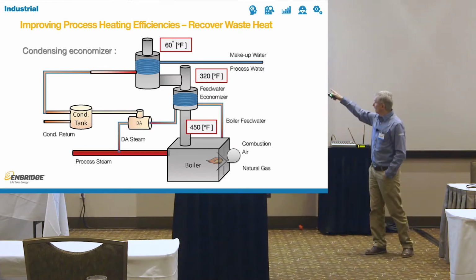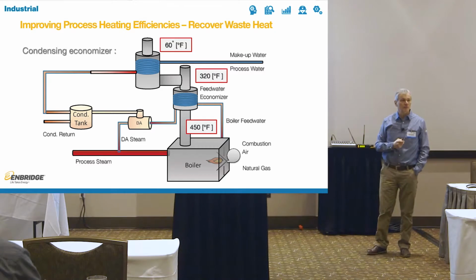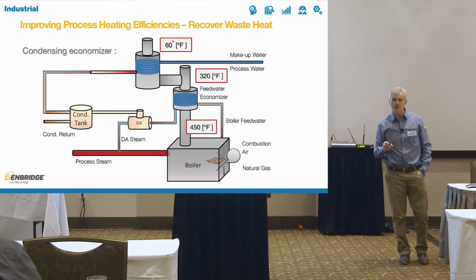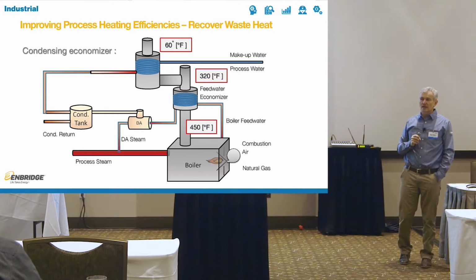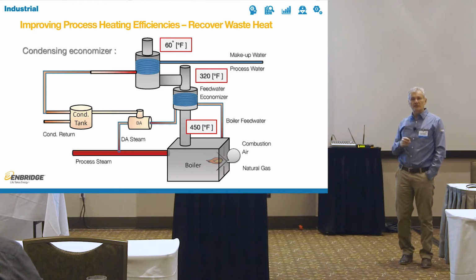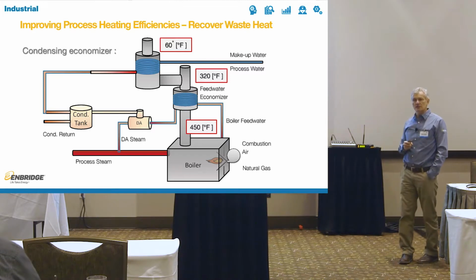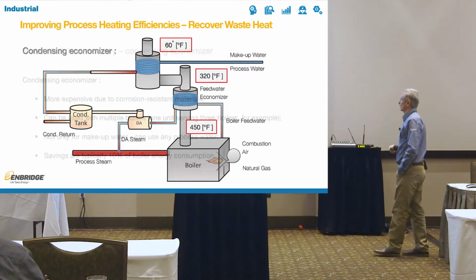As a matter of fact, I didn't even put Feedwater Economizer on the system. I just put the condensing economizer, and I didn't tie it to the boilers at all. I tied it all to the process. And we saved close to 700,000 cubic meters a year. You'll see that example later.